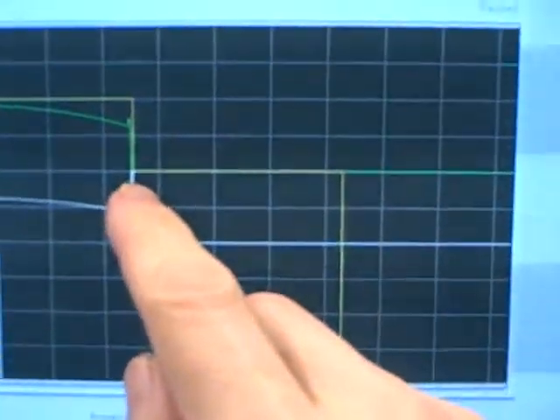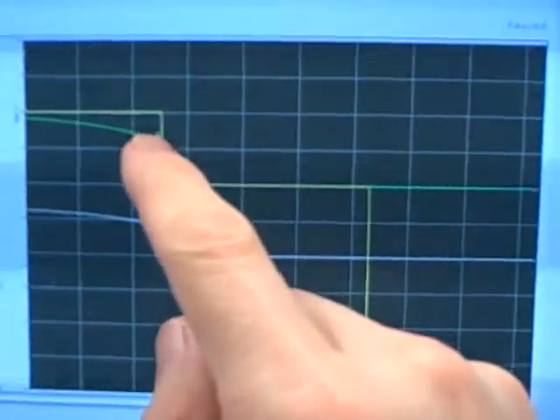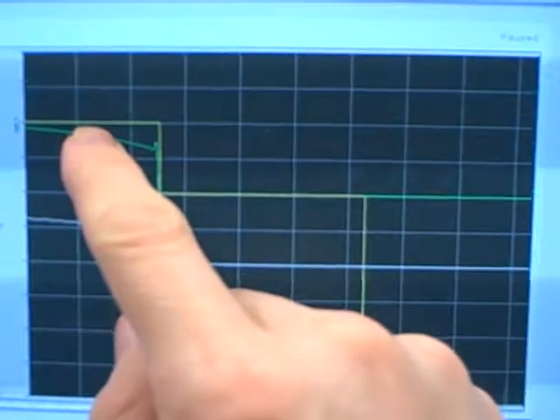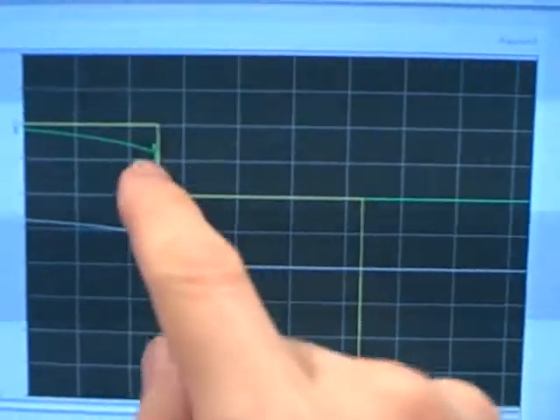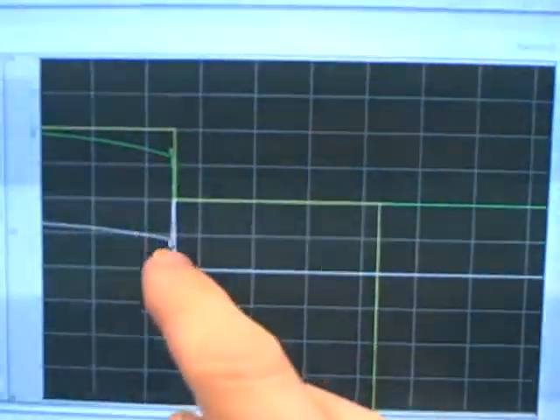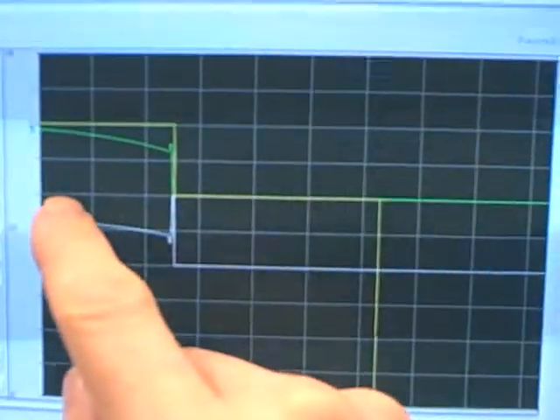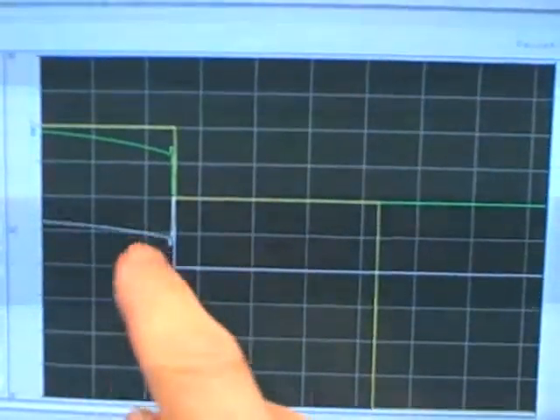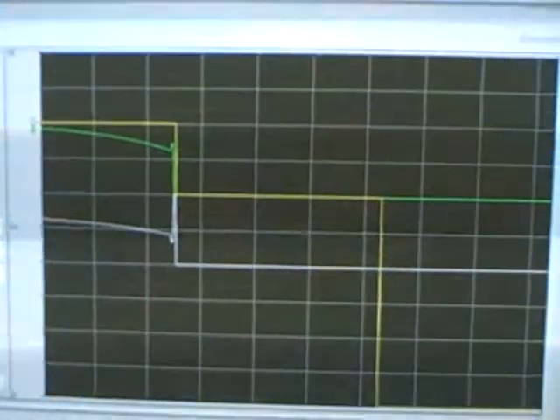Here's why. In order for the process variable value to porpoise, it has to go up, then reverse direction, then reverse direction again on its way to set point. Integral action will never ever do that, because so long as we're always below set point, integral always keeps driving in the same direction. It will never reverse action. It will never reverse direction.